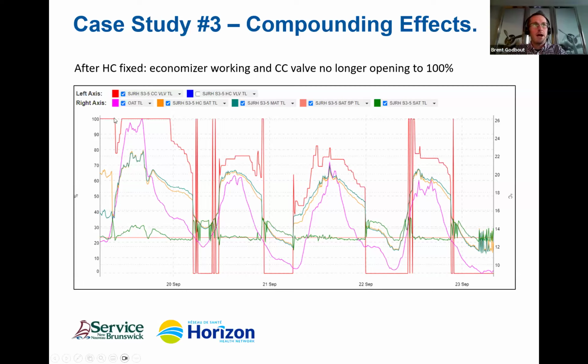While we were leaking or passing on our heating coil valve, we weren't taking advantage of that free cooling because we couldn't get to our set point. So our chiller overnight was being loaded higher than we needed it to be unnecessarily. So that's the compounding effects of these things.